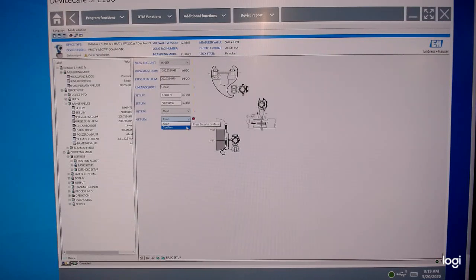Coming down, 53, 52, 51. We're at 50, 50, okay, and it looks like I got 50 on my PAT calibrator. I'm going to go ahead and confirm and hit enter. And you can see I got 49.994736. Well, that's about the best I've ever done in my life at hitting 50 right on the spot. So what it did is it recharacterized the sensor to an upper and lower range value associated with these 2 points right here. So this procedure is now done.